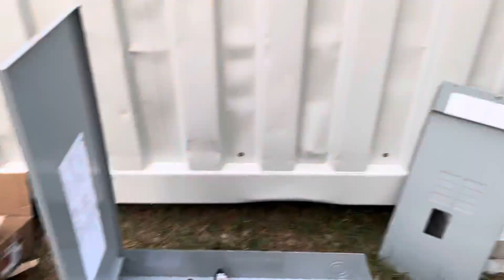Now, for some reason, if I need to bypass all this equipment in here, the equipment wasn't working, the batteries failed, or PV panel, whatever the reason, I can switch this transfer switch. Depends on which side. I hadn't decided which one's going to be my utility line or my solar power line. Whichever one I can switch. If say the utility's on top, I can throw the switch on top. It will then send my power from the utility straight to my transfer switch. And it'll bypass everything inside this building.